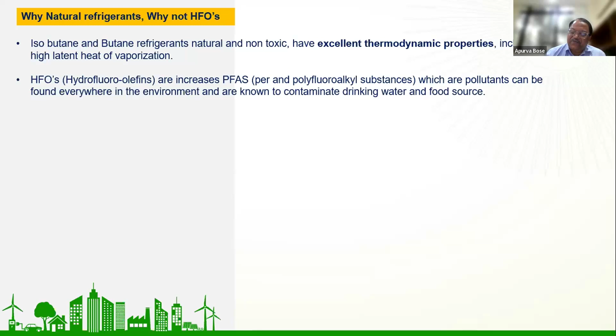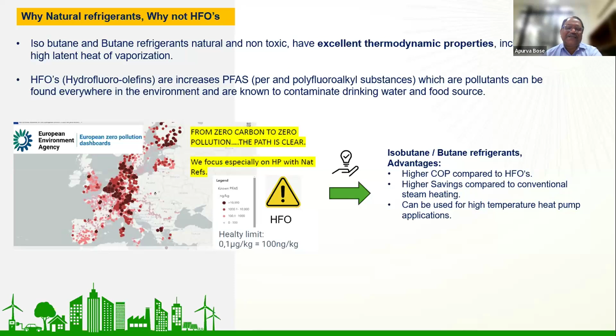That's where some other natural refrigerants also play a critical role. When I was talking about the CO2 based heat pump, I was mentioning that the delta temperature is supposed to be more, but in many places the delta temperature is not high. Let's say the heating solution is required at 115 degrees Celsius, but the return is around 105 degrees Celsius or so. That is when CO2 is not advantageous to use. In that case we can use isobutane or butane refrigerant. Similarly, when we talk about chilling, if the delta T is not high, we can think of using propane. Moving on, actually this is it. So that's all from my side.